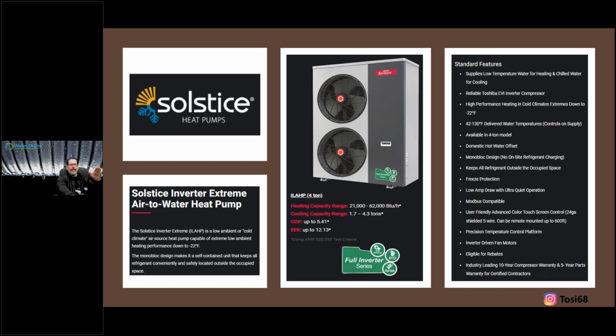There's a slide that shows what outdoor temperature I can absorb and then add, right? It can only do so much. So we need to understand where our design day temperatures are, what our heat loads are for our envelope, and then we can design around that. That's where all things start. It has to be, right?